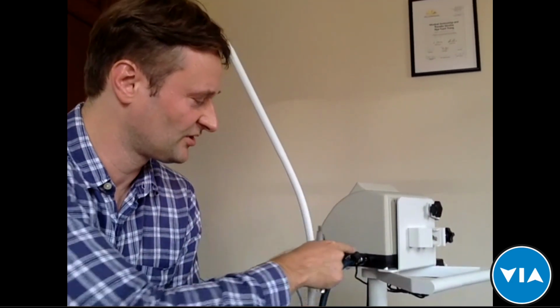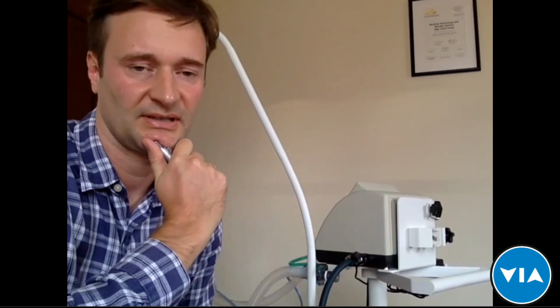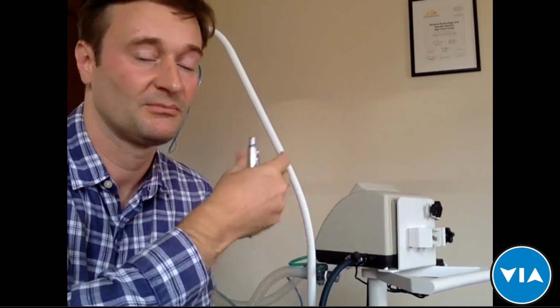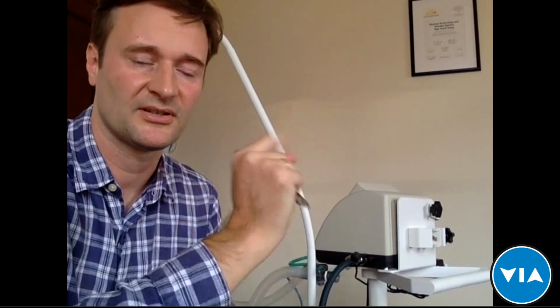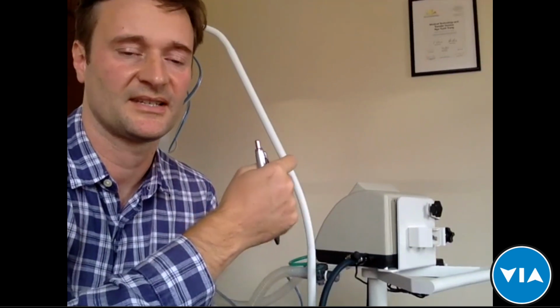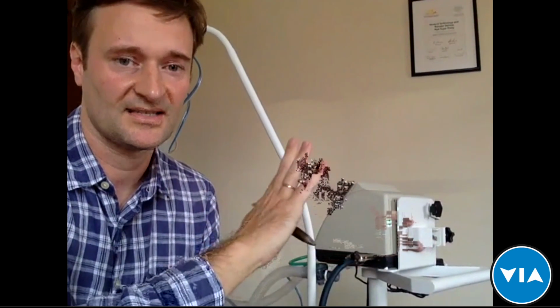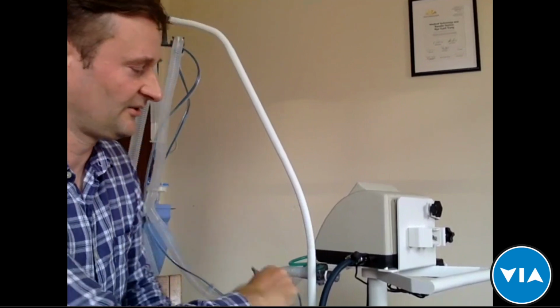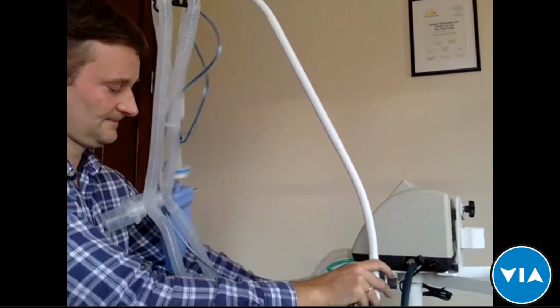And batteries last for 4 hours, and the batteries always stay there. They can be charged by an AC power source. So there are 3 elements inside that can potentially be changed: the battery if necessary, almost never; the oxygen sensor every 2 years, let's say; and the filter every 6 months. And that is basically it. So it's a very, very low maintenance device. And that's all I wanted to share with you today, and I'm now open to questions. If you have any, please go ahead and ask. I will try to answer everything you have.